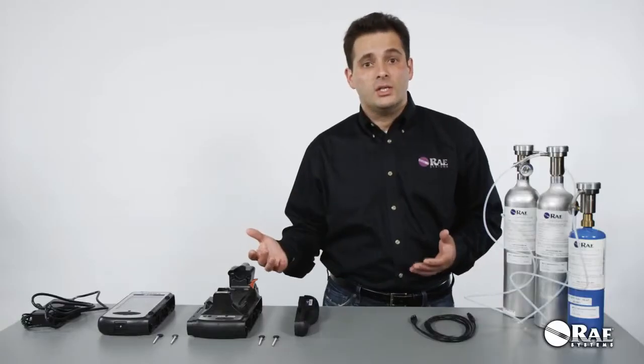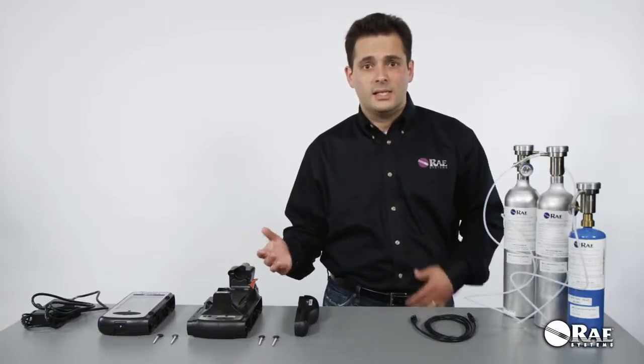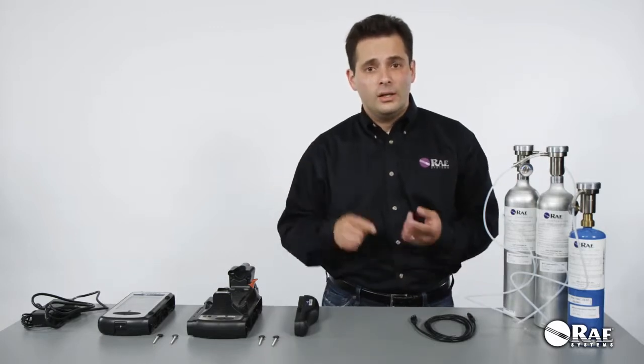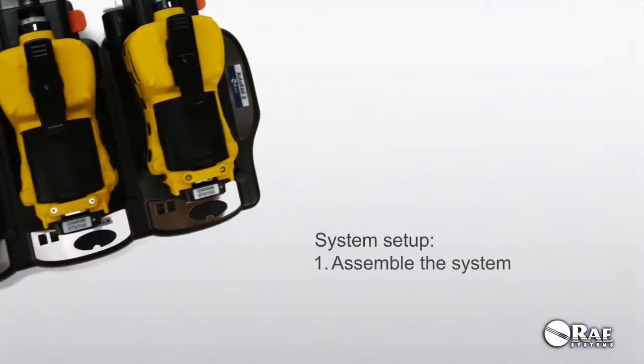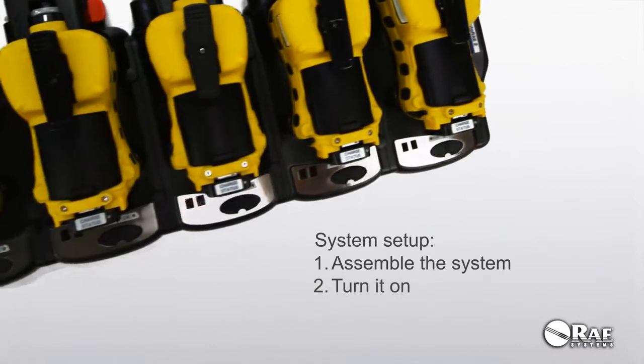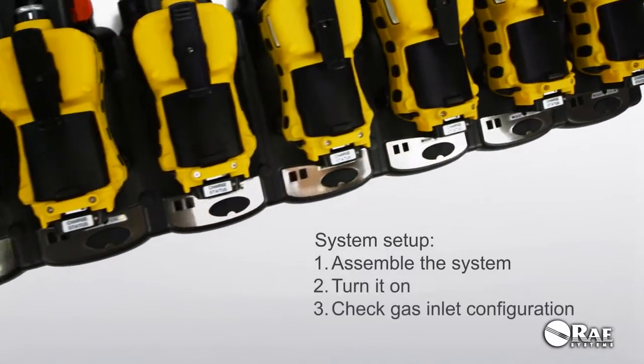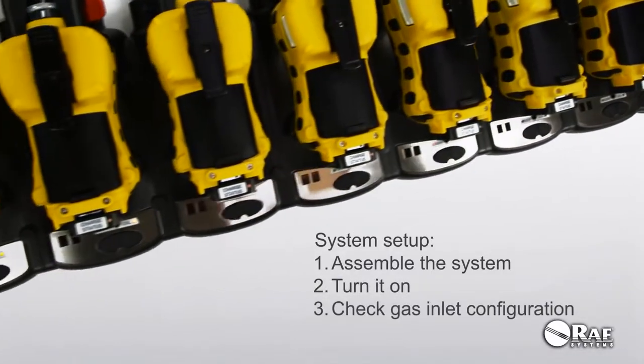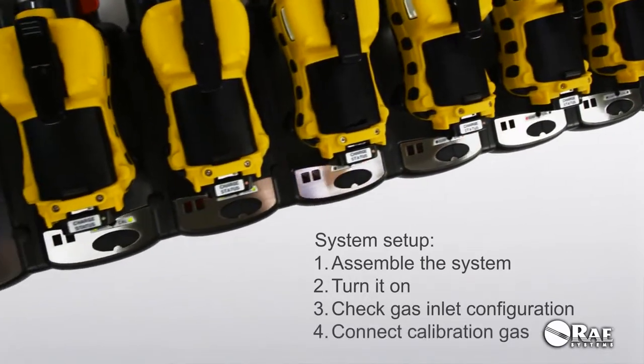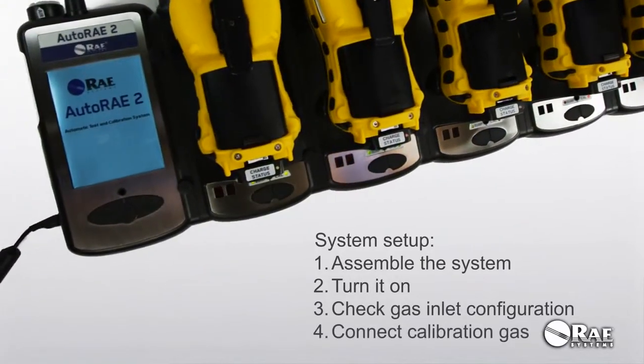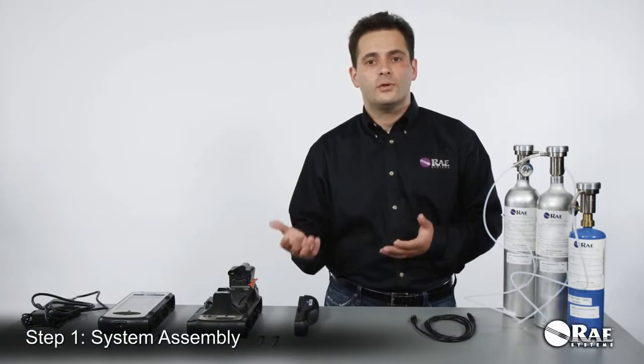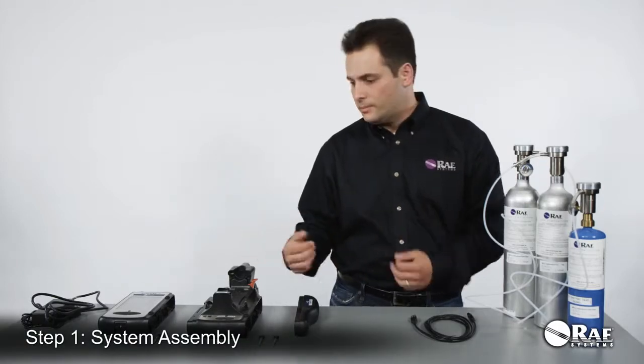So the setup process is very simple. It consists of 4 steps. 1, you need to assemble the system. 2, turn it on. 3, check and make sure that gas inlets are configured properly. And 4, connect the calibration gas cylinders to the system. So let's start with the first step, the assembly.